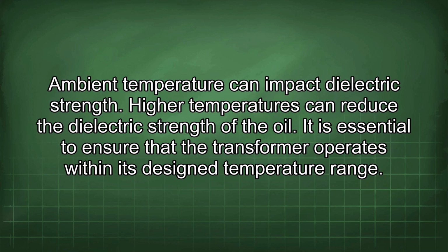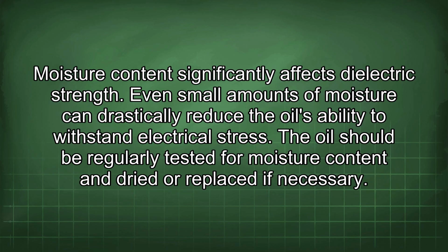Ambient temperature can impact dielectric strength. Higher temperatures can reduce the dielectric strength of the oil. It is essential to ensure that the transformer operates within its design temperature range. Moisture content significantly affects dielectric strength. Even small amounts of moisture can drastically reduce the oil's ability to withstand electrical stress. The oil should be regularly tested for moisture content and dried or replaced if necessary.